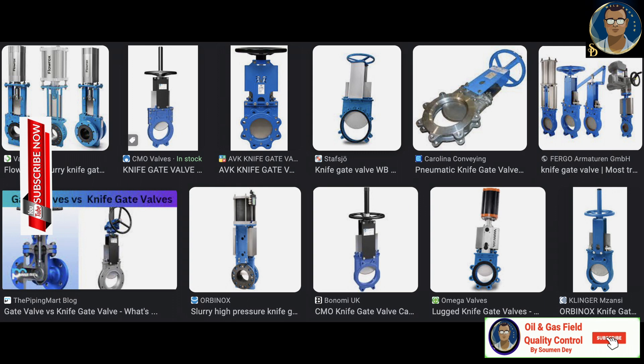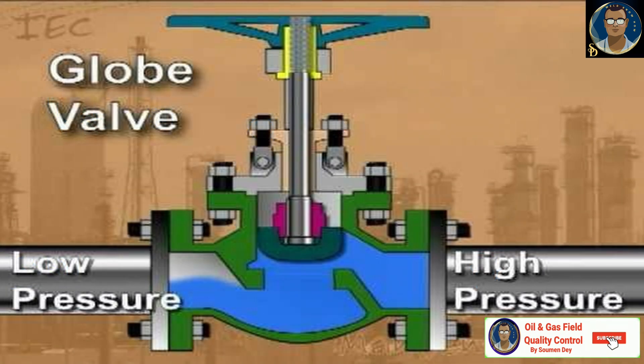Knife gate valves are used for controlling flow of media containing solids. The knife gate valve features a thin gate controlled through linear action that cuts through materials and creates a seal. These valves are not suited for high pressure but are ideal for use with grease, oils, paper pulp, slurry and wastewater. Globe valves are typically applied in modulating control operations and are available in three body types: T-body, Y-pattern and angle body.